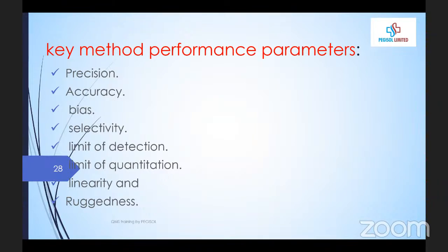Precision is the ability of the equipment or the method to produce a consistent result. Let's say, for example, for an equipment, you are validating glucose. If it's giving 4.1, 4.2, 4.3, 4.5, 4.6, 4.7, 4.8, 4.9, 4.8, 4.2, it shows you that equipment is precise. But something can be precise and yet not accurate. True or true? True. So something can be precise and yet it's not what? Accurate. I want to say interesting, but confusing. Okay, that's why we're here to explain. Please jot down your questions, and as we go along, I will explain. Now, accuracy is the ability to produce closeness to the real result, or to the original expected outcome. Bias is either above or below. It's on one side.